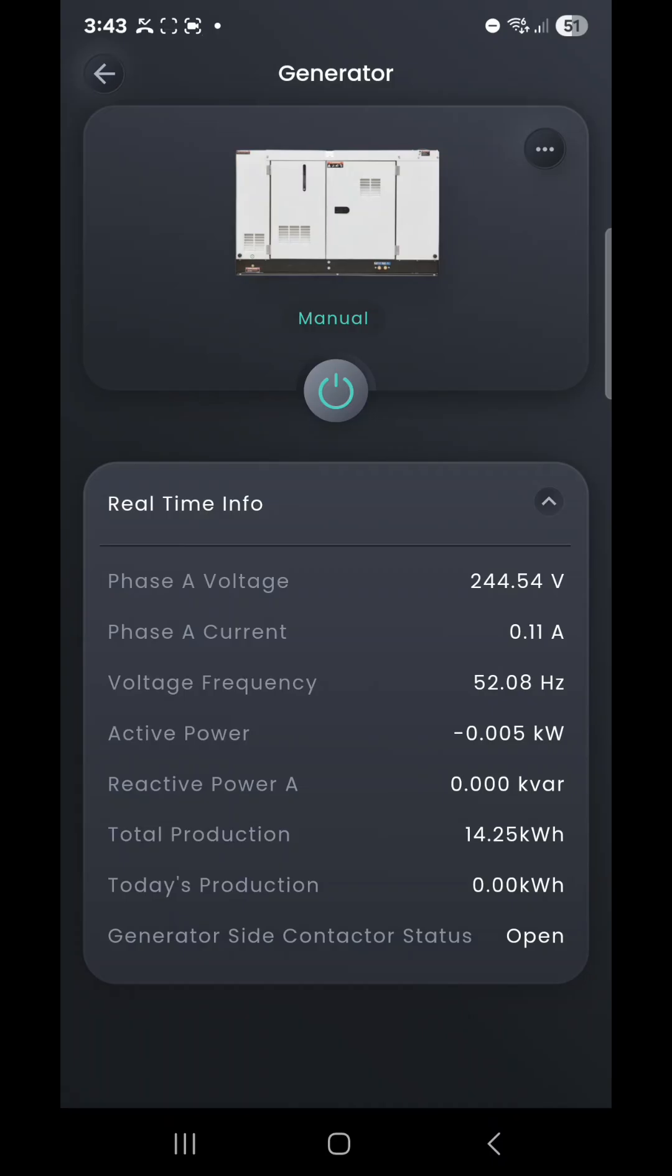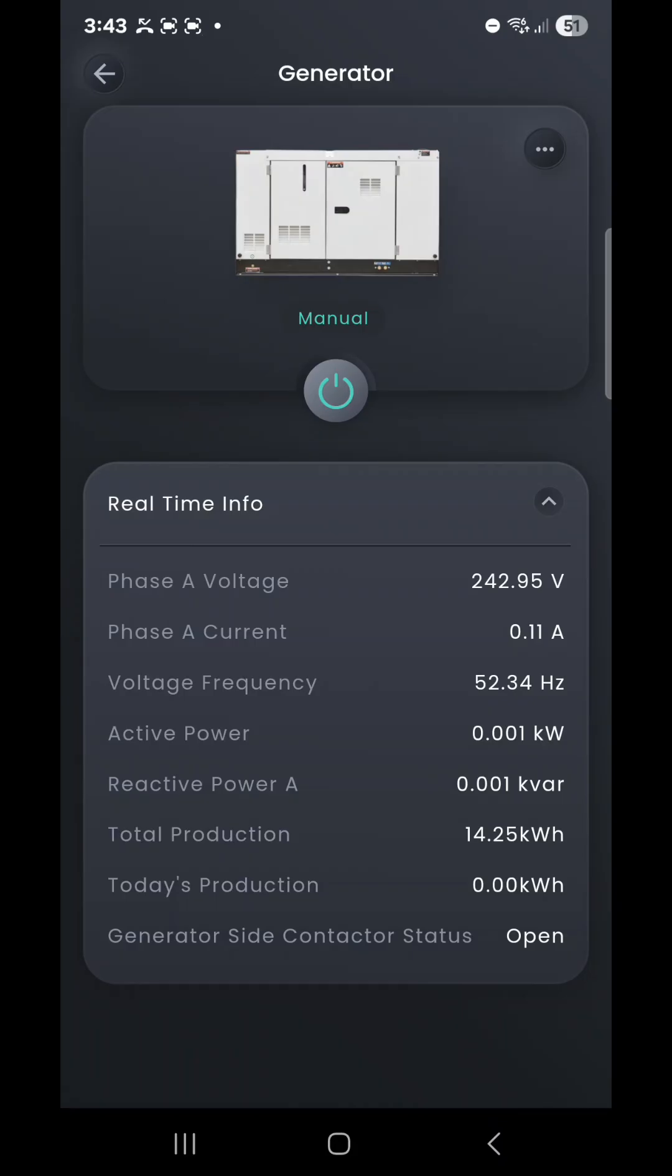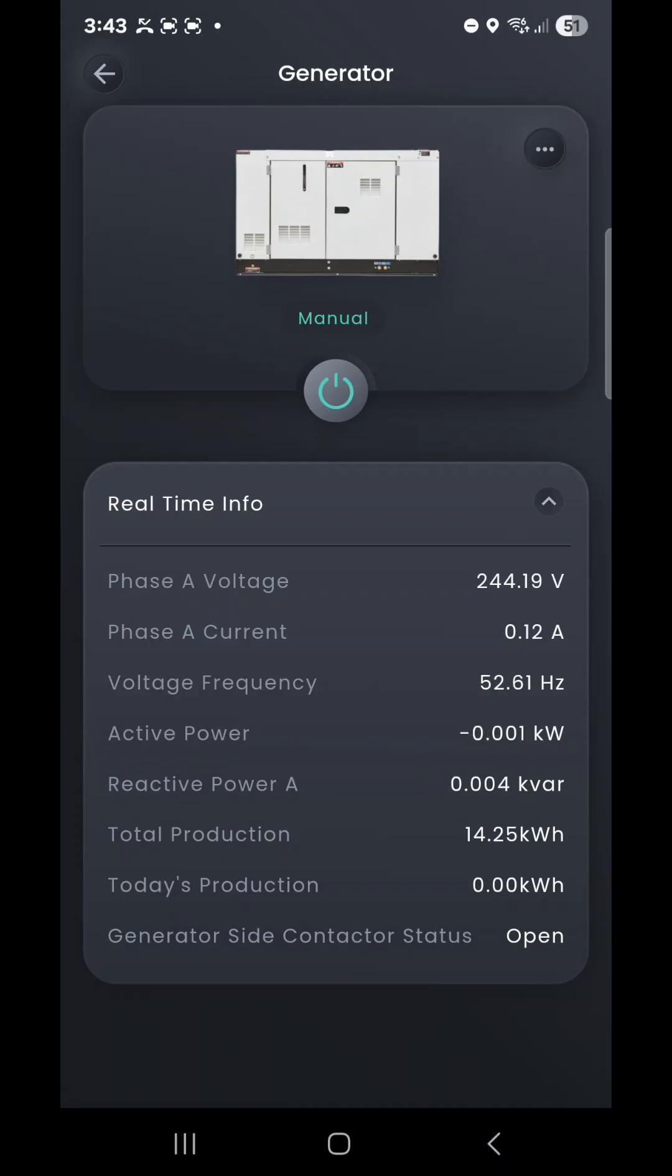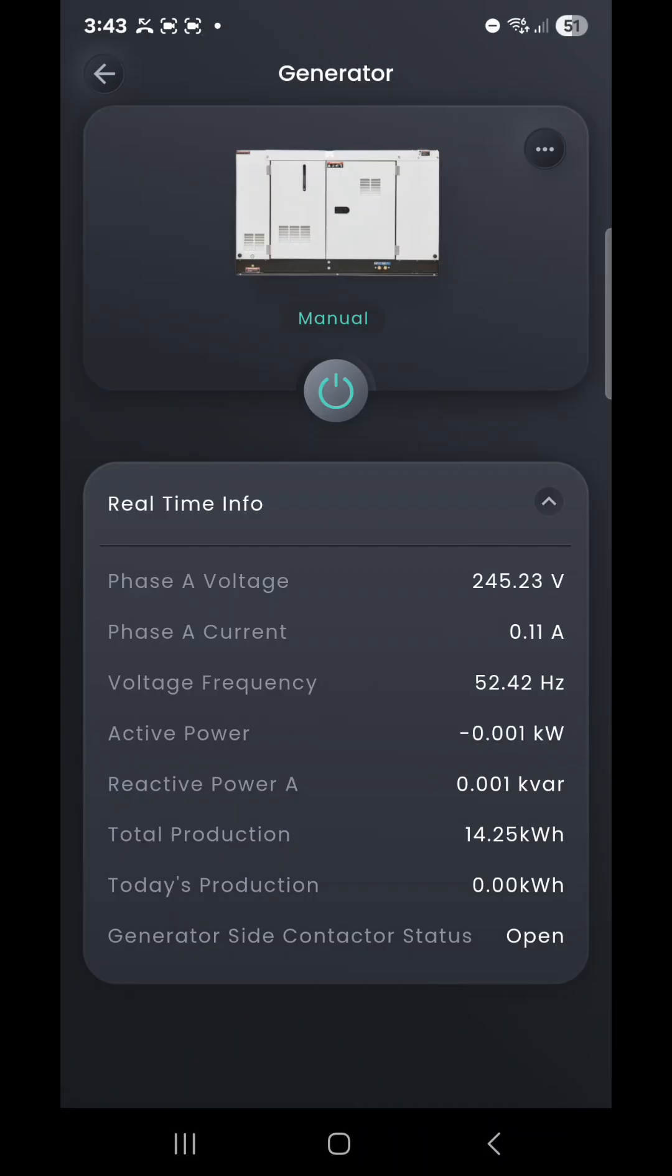If we look down below: Phase A voltage, Phase A current, voltage frequency, and then active power. If the system doesn't need to actually receive any power from the generator, this figure will often be negative or close to zero. If the system can take the generator power input, that kilowatt active power will actually start showing in kilowatt increments, so it'll be 1,000 watts, or one kilowatt, two kilowatt, and so forth, depending on the size of the generator and its setting for its input.